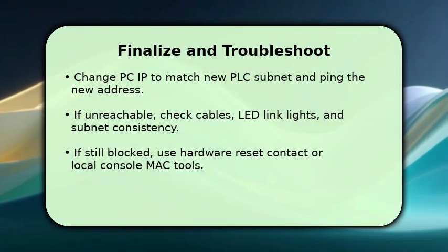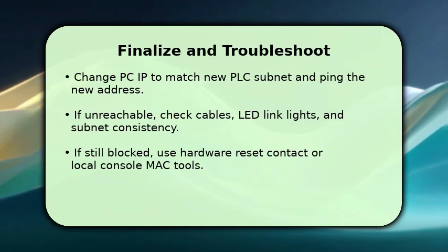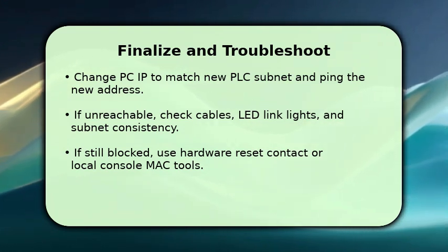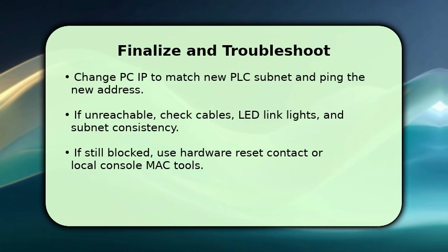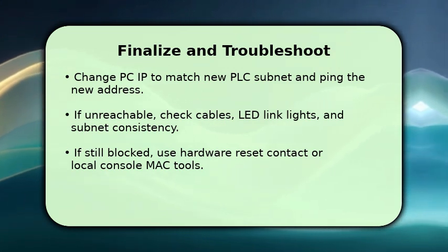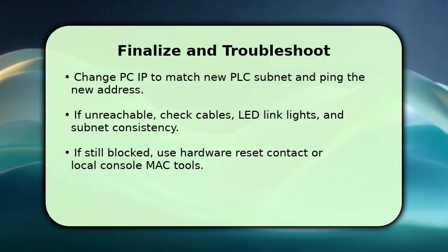Finally, switch your PC back to the PLC's new subnet and ping the address to verify. Make sure LEDs show link and activity. If ping fails, recheck the subnet mask, gateway settings, and physical connections.